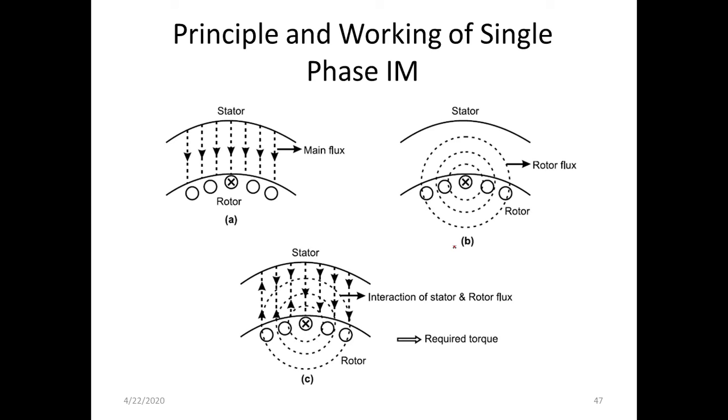Now, principle and working of single phase induction motor. In case of single phase induction motor, the supply is single phase. The single phase supply is not capable to produce a rotating flux. For producing a rotating flux we need at least two fluxes. For this reason, single phase induction motor is not a self-starting motor.